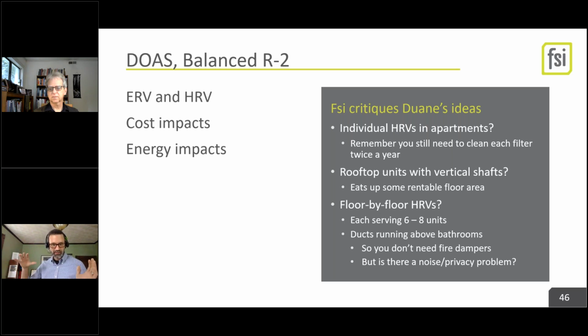So up to 10% can leak from the exhaust side, which is in residential, that's mostly restroom and kitchen, individual people's kitchen, not commercial kitchen. And it would be allowed to be 10%, and most manufacturers come nowhere close to that. They've got a couple percent. It's something we've been thinking about in a post-COVID world. Maybe we want to put a UV light in there also to be that extra level of protection, just to know that that little bit of bypass was not an issue.